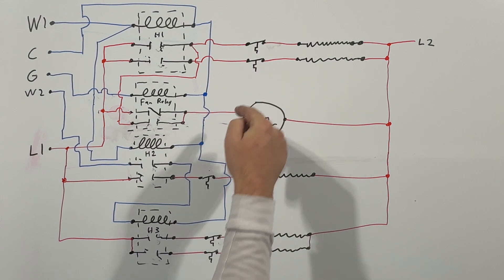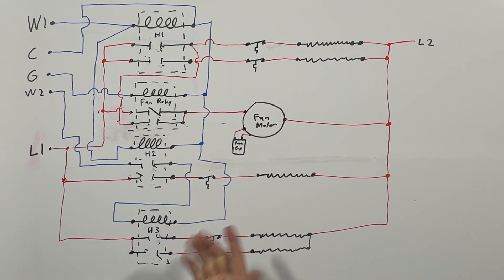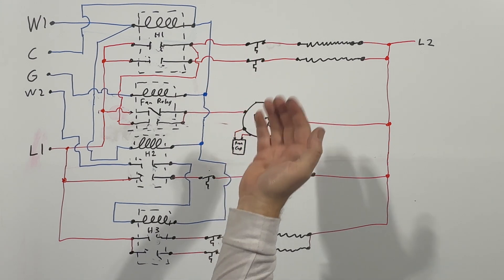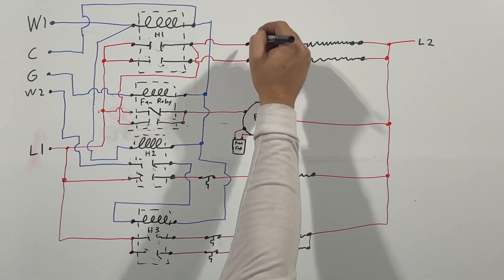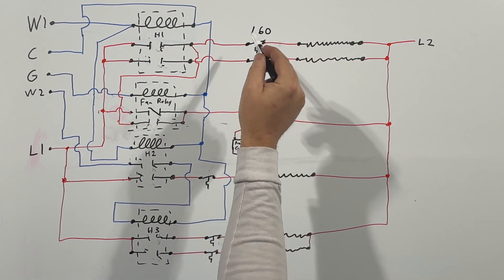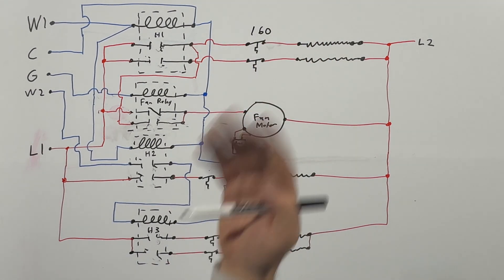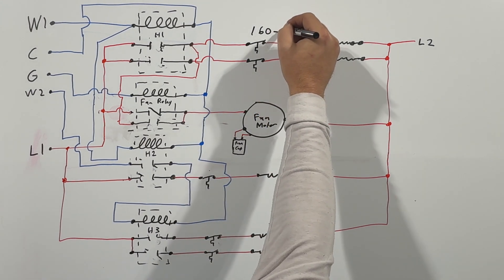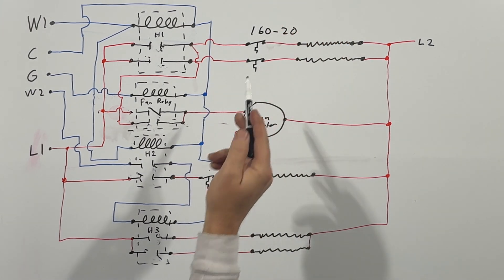This is pretty much your normal setup, and then keep in mind every single element will have a high limit or a temperature switch. So if it gets too hot, it will open on rise. So I think in this case these were 160 degrees on rise, so basically if they reach 160 degrees they pop open.